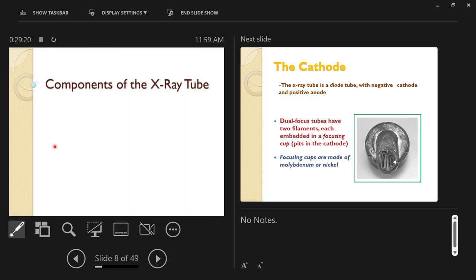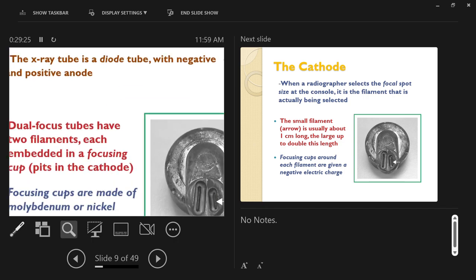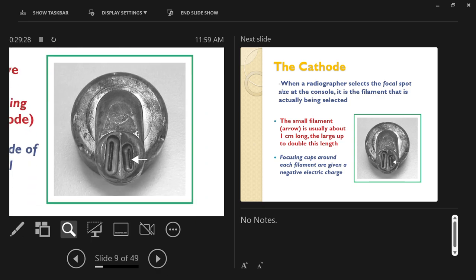This cathode has two filaments — it's called a dual focus tube. Your machine can access one or the other, or you can tell it which one to use. It may prevent you from accessing one if you enter the wrong factors; for example, if you select high kilovoltage and high milliamperage with the small focal spot, the machine might not allow that.